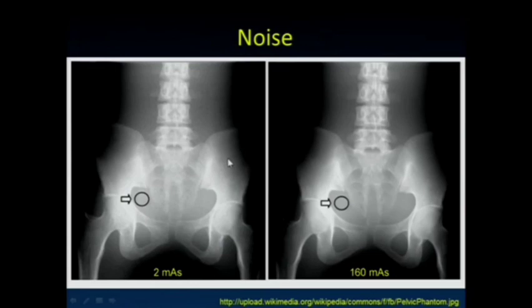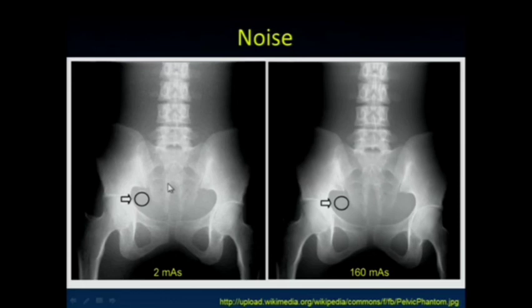Just as an example, here's a phantom of a pelvis radiograph obtained with 2 milliamp seconds, so current times time, and here at 160, 80 times more mAs. You can see the speckling here compared to here. Here's a contrast versus resolution versus noise. We've got some different size disks, and they're in a background setting of some noise, and there's a column of them which are higher contrast than the next column and the next column. You can really get a feeling for how both contrast and spatial resolution, in conjunction with noise, play a role in how conspicuous a lesion is to us. There's an interplay between all of those quantities.